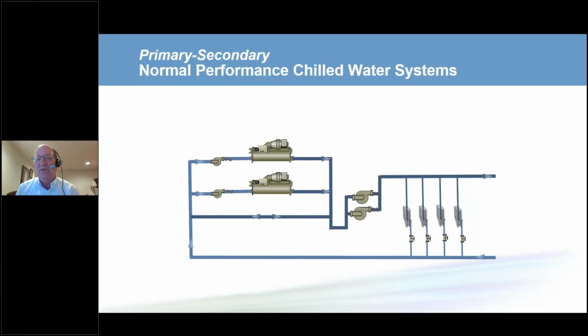But before we can talk about high performance chilled water systems, we need to start out with what's normal performance. As was mentioned, I began my work in the industry in 1982, and that was before all of our hosts today were born. That's happening more. But in 1982, the pinnacle of chilled water systems was a design called the primary-secondary system, or the decoupled system. In a primary-secondary system, we have a chiller and we have a pump per chiller. The flow through the chillers is constant through their evaporators. We have two-way valves out in the system, and those two-way valves modulate and change the water flow not only through the valves, but also through the system. These secondary pumps, or distribution pumps, have variable speed drives, and those variable speed drives change their speed and save pumping power when the valves close.